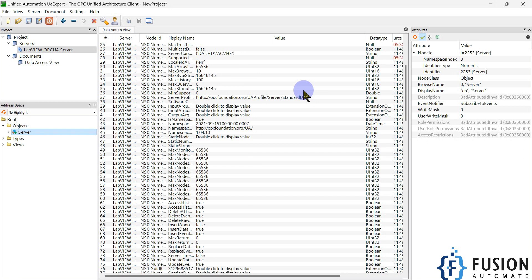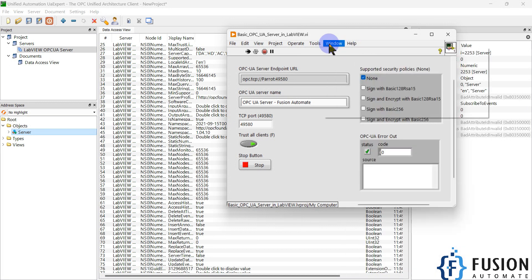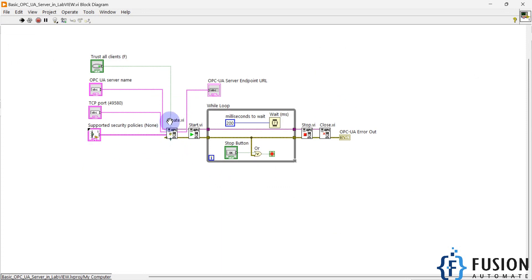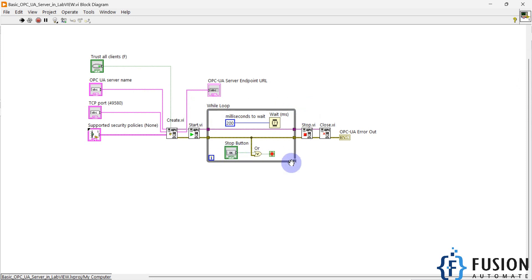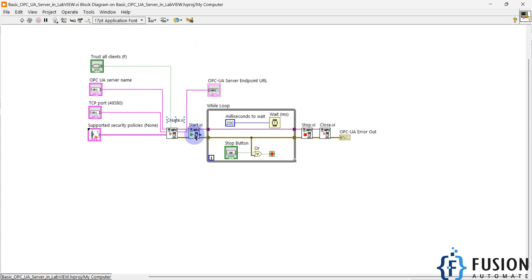If you want to see how we programmed it, click the Window button, then Show Block Diagram. We used the Create VI to create our OPC UA server. To start the server we use the Start VI, which runs continuously in a while loop, updating data every 200 milliseconds. Once you click Stop, it turns off the while loop, stops the OPC UA server, and closes all connections.